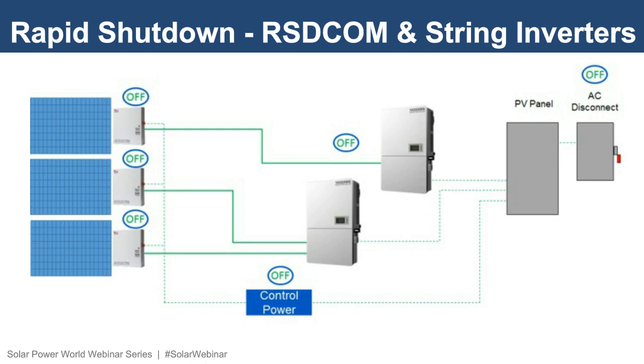In a similar fashion, the rapid shutdown combiners will lose their control power. When this happens, their internal contactors will open, which isolates the PV output conductors from the PV source circuits. Lastly, the bleed circuits internal to the rapid shutdown combiners will help drain any inverter bus capacitance that may be still energizing the PV output conductors. Assuming the installer did their part to label and identify the system appropriately, you'll have a code-compliant system.